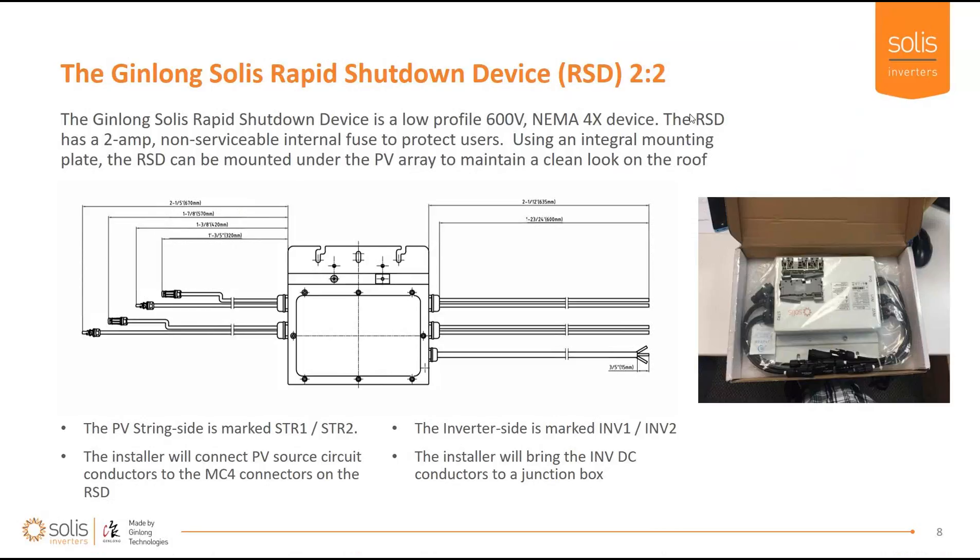The Ginlong Solis rapid shutdown device comes in two versions: a two-input two-output unit and a one-input one-output unit. The device also includes two terminals to connect it to the inverter. It's a relatively small package that can be mounted underneath the modules for a clean aesthetic. It has a two-amp non-serviceable internal fuse to protect workers. There is a PV string side marked STR1 and an inverter side marked INV. You must install this in the right direction — PV source circuits come in on the string side, and PV output circuits leave the device going down to the inverter MPPT connections on the inverter side.